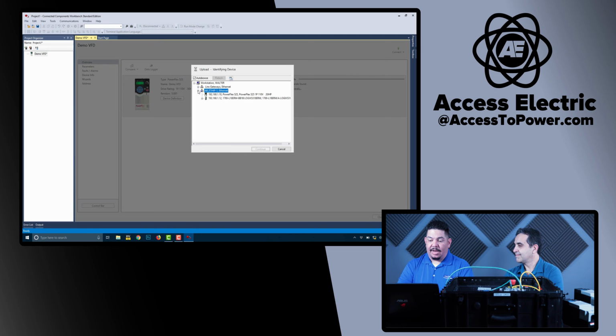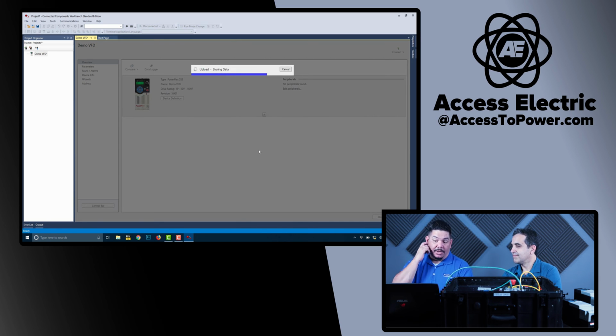This AB Ethernet IP driver should be where we see it. And we actually can see the three main components of this system. The Stratix switch, which is .11, and the PLC, which is .12. But the drive is .10, and we can go directly online with that. So we hit continue, select it here, hit continue.